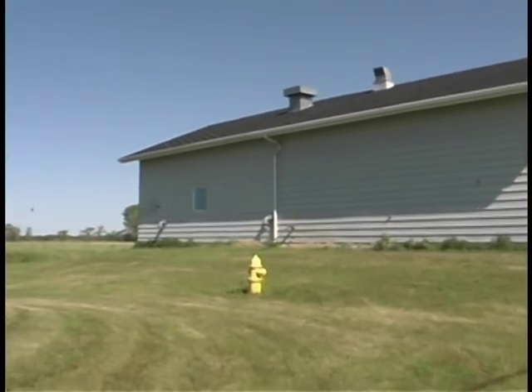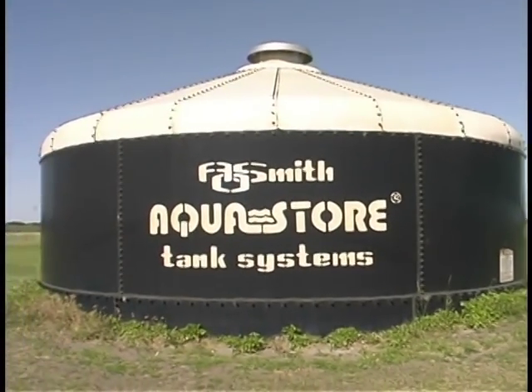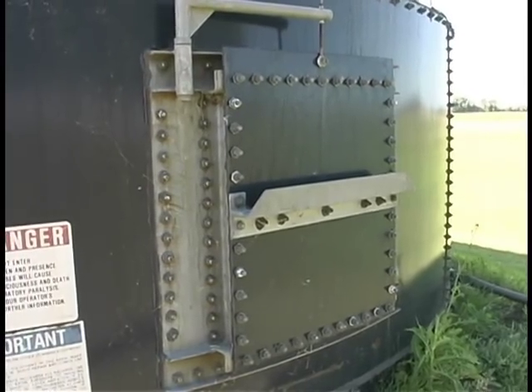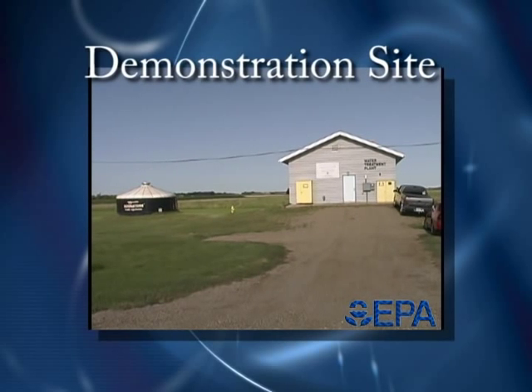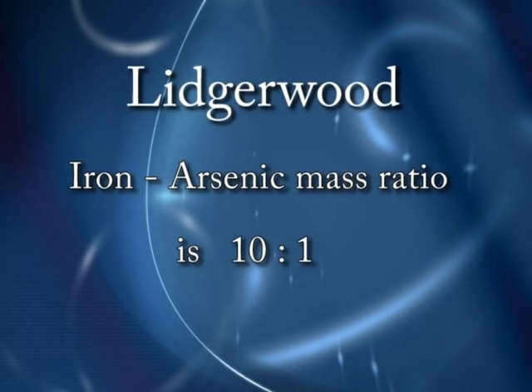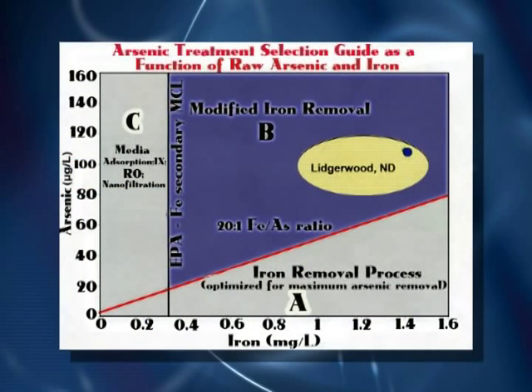The sludge is pumped to a dewatering tank and hauled to a non-hazardous landfill at about 20 cubic yards every two years. The EPA demonstration technology for this system was a modification of the existing system to add more iron, since the natural iron-to-arsenic ratio was only about 10 to 1, placing the system in zone B.